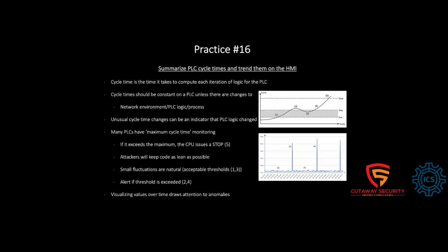We talked about a few of the validation practices for integrity checks. Now let's talk about monitoring. Practice number 16 talks about summarizing PLC cycle times and trending them on the HMI. The cycle time is the time it takes to compute each iteration of the logic in the PLC. Most PLCs give you the option to display it, or write it to a register that you can copy. Most PLCs also have a Tmax cycle time that will shut down the PLC because it's overloaded, because the CPU usage is too high. However, most code typically uses 20, 30, 40% of the CPU time, and the cycle time for the PLC is within a tolerable range. In a deterministic PLC, this is predictable.